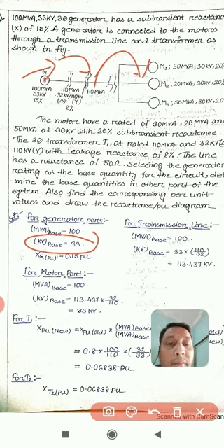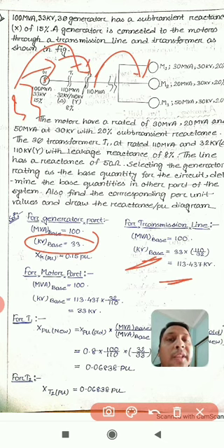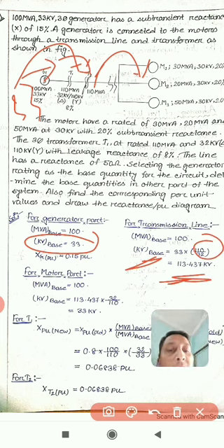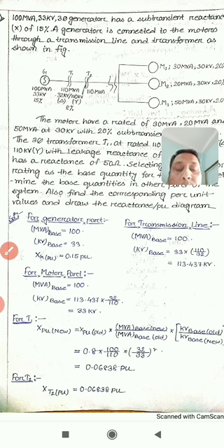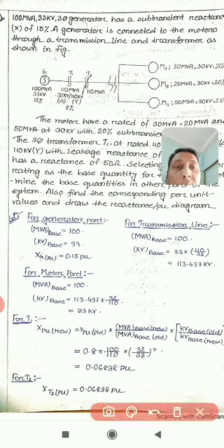You can see in the transmission line what your kV base will be, because of the transformer ratio of 110/32. Accordingly, the 33 kV here jumps to this side with the ratio of 110/32. So the base for the transmission line becomes 113.437. You can check the calculation. And then go for the motor load. For the motor load, again you jump from this side to this side.